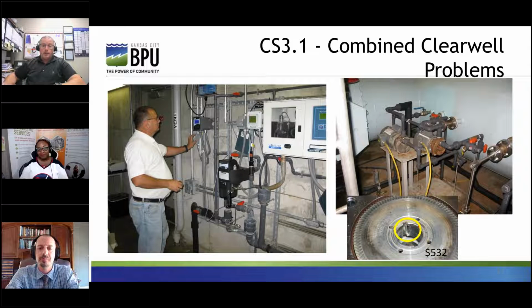Parts and maintenance, time to rebuild the oversized pumps was excessive. Air was causing damage to the pump impeller over time. You see in the photo above, it would damage the keyway and actually drive it into the stainless steel impeller. A complete new pump was $1,500 and spares were expensive. Rebuilt pump and parts cost around $500 or $900 to rebuild that pump, not including its installation, and keeping spares to rebuild those pumps was expensive. So it causes other problems.